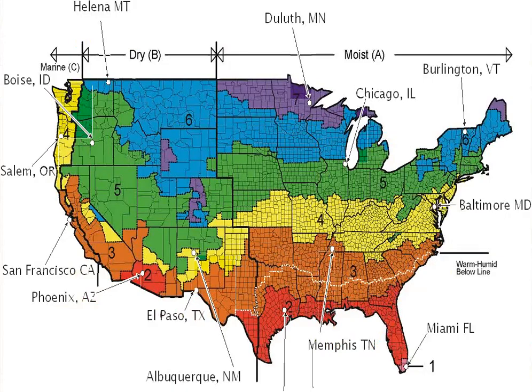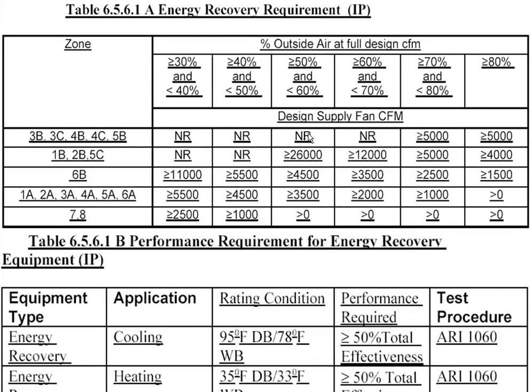But let's take a look at the map, what they've broken down with addendum E. We've broken down requirements into actual regions on the map. If you look here, we've got Zone A on the east side of the U.S., which is a moist area. This is where we have some humidity factors we have to take into consideration. On the west side, we have Zone B and Zone C. So we have our coastal climates along the Pacific region, and then we have the west, where we know we have a lot more drier air, drier climate. And then we've broken them down from 1 to 8, going from the southern part of the country up into the colder areas, 8 being obviously Alaska, 7 and 8 being the colder climates.